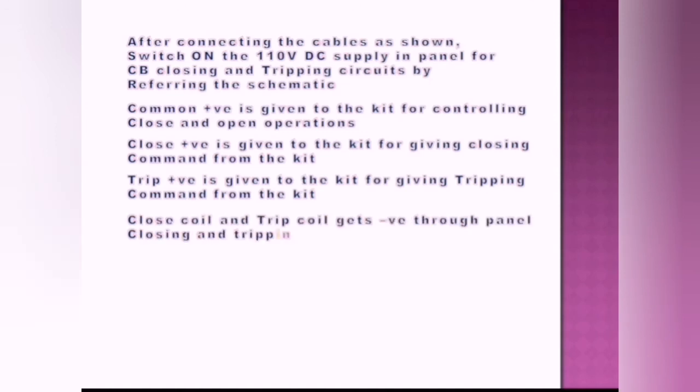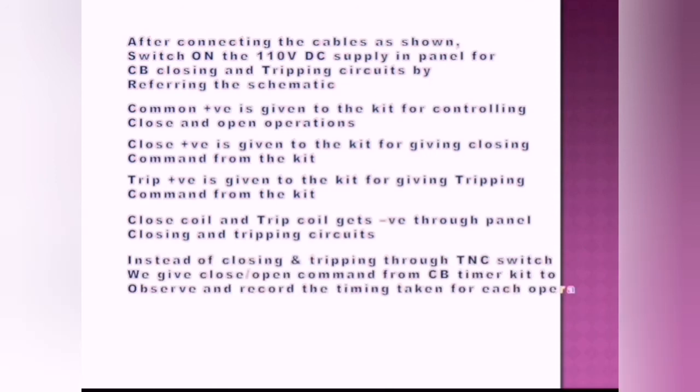Close coil and trip coil get negative through panel closing and tripping circuits. Instead of closing and tripping through TNC switch, we give close and open commands from the CB timer to observe and record the timings taken for each operation.